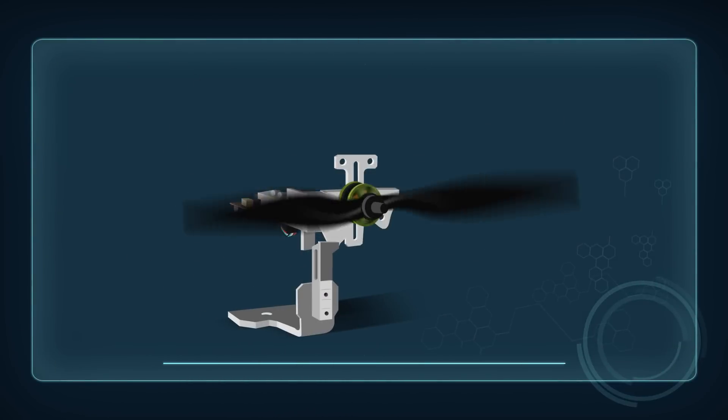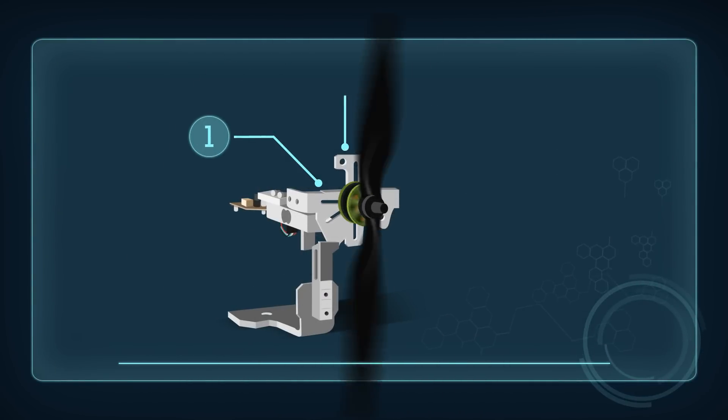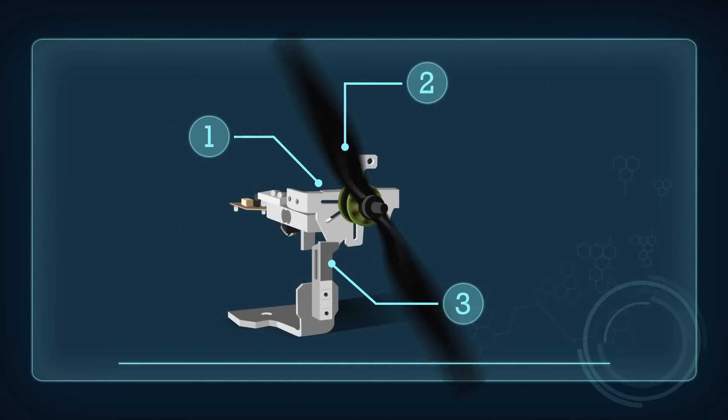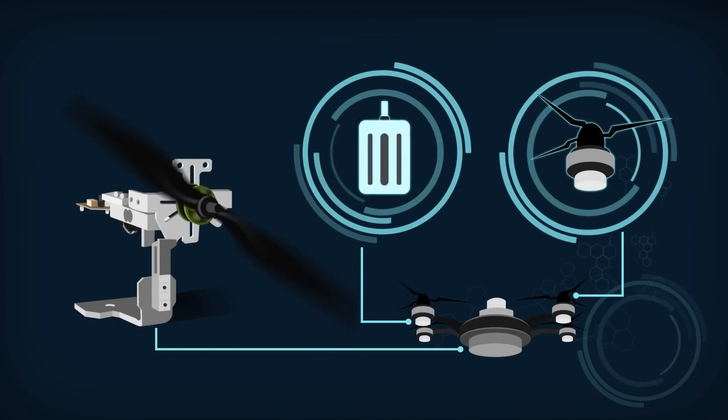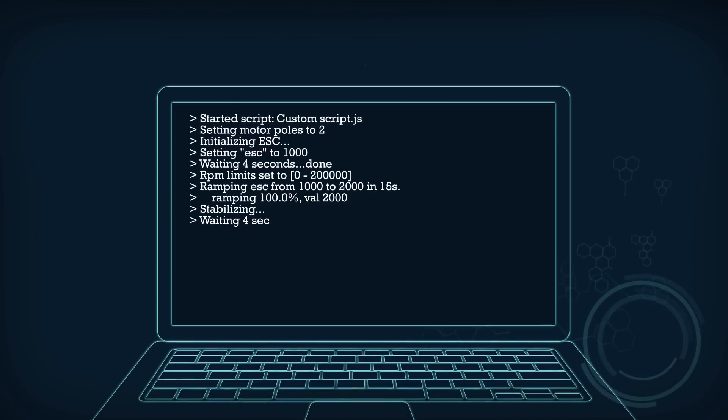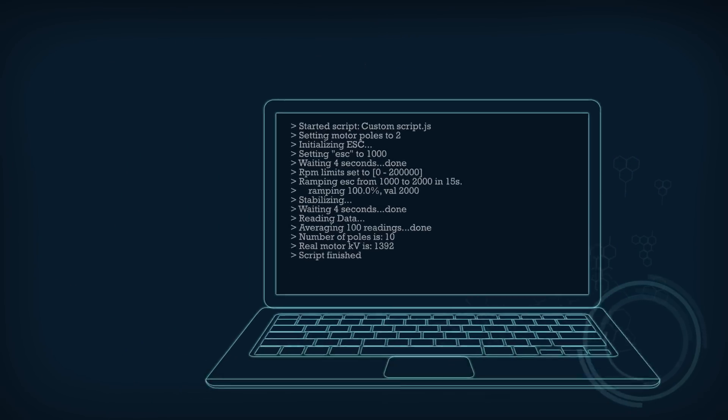These three features set the RC Benchmark apart from other dynamometers and will greatly improve your design workflow. It directly measures the efficiency of the motor and propeller, has automatic testing and powerful scripting abilities, and exports data easily to Excel or MATLAB.